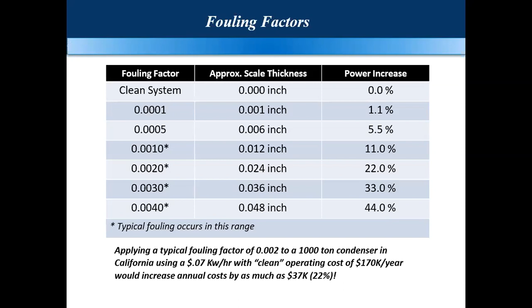So basically, your chiller is doing more work, and the chiller is having more kW per TR, you can say. With a 0.001 increase in the fouling factor, we have seen an increase of 11% in the total electricity consumption. So filtration and water treatment go hand in hand. What I said previously: it obviously reduces corrosion, scaling, fouling, and biological activities.